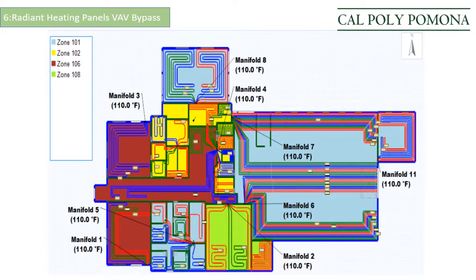By analyzing the operative temperatures, the team found that if the heating panels are installed on the ceiling or the walls, the view factors of the radiating surface would affect thermal comfort. For higher height spaces such as the service stalls, if the radiator surface is installed on the ceiling rather than the floor, then the operative temperature is predicted to be within 80% of acceptability from ASHRAE 55 while using less energy. Mean radiant temperature simulations suggested significant variance in operative temperature in spaces that have one or more exposed walls. By installing the loops around exposed walls, thermal comfort in those spaces would be improved.